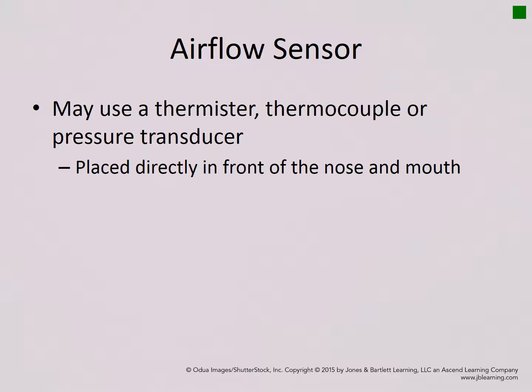The airflow sensor, we can use either a thermistor or thermocouple or a pressure transducer, and this is placed directly in front of the nose and the mouth. I explained this one more in week 1 on the monitoring equipment. The thermistor and thermocouple get their signals from temperature, whereas the pressure transducer is the most accurate representation of flow volume. Really, you should use either a thermistor or thermocouple and a pressure transducer. So 2 sensors to measure airflow. The pressure transducer is for identifying hypopneas because it's so sensitive, and the thermistor is used for identifying apneas because it's less sensitive.